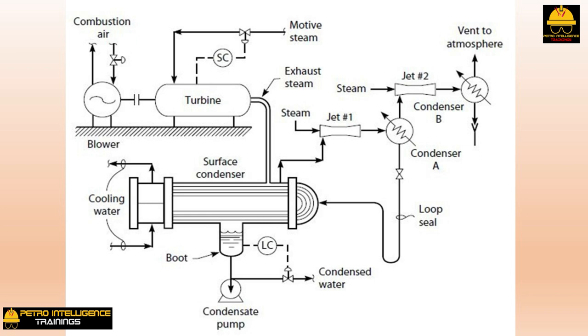The purpose of the loop seal: the pressure in condenser A is greater than in the surface condenser but less than in the final condenser B, meaning condenser A operates at vacuum conditions. This prevents condensed steam in condenser A from draining to atmospheric pressure unless the condenser is elevated by 10 to 15 feet. To avoid this, condensate is drained back to the lower-pressure surface condenser. A loop seal prevents non-condensable vapors from blowing back. The height of this loop seal must exceed the pressure difference in feet of water between the surface condenser and condenser A.